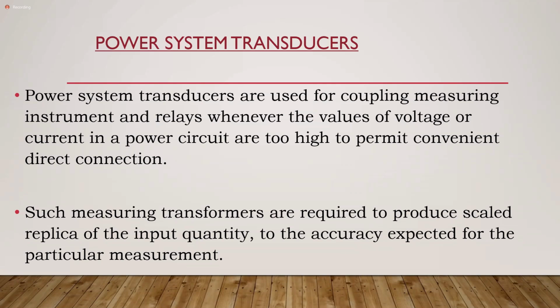and two, which means that the customer is paying more than they ought to. And the reverse is true. If we are not getting that scaled replica, that accurate representation of what's on the system, then we can also have a situation where the utility is not getting what it ought to. So accuracy is important where measurement is concerned, because in terms of measurement, that is money.